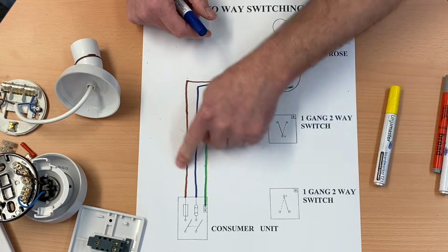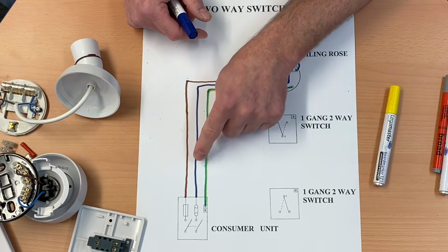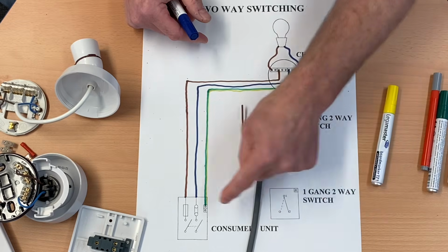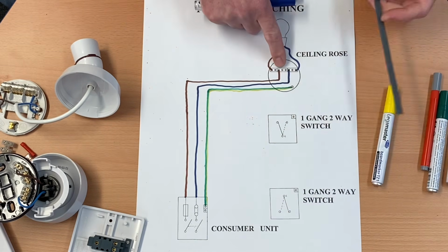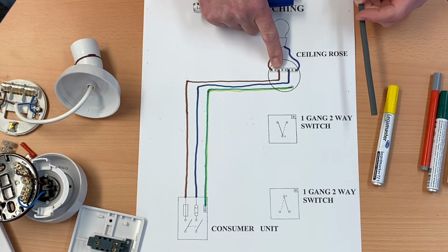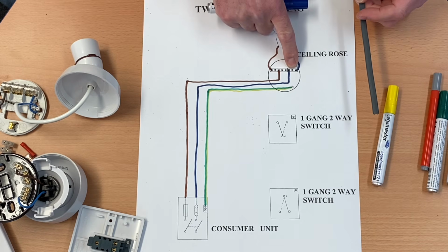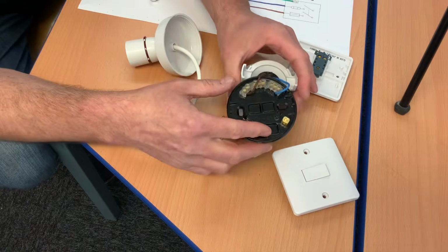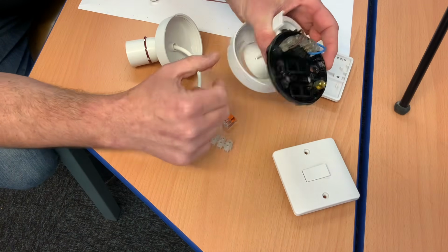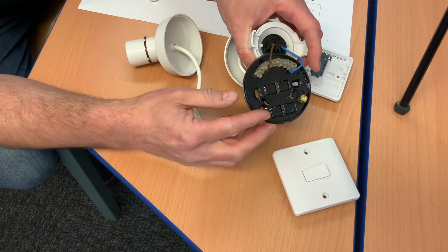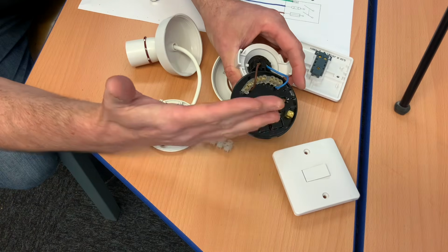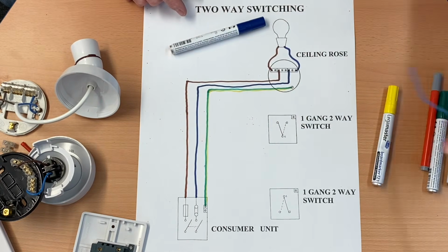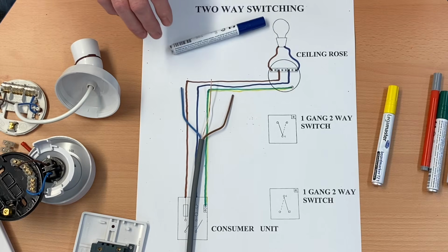Okay, so that brings our first cable in. So it's come from the consumer unit, line, neutral and CPC. So line, neutral and CPC is brought in like so. And it's connected into the loop, any of the 3, it doesn't matter which one. Into the neutral, any of the 3, doesn't matter. And into the terminal, which is for the circuit protective conductor, like so here. Remember, fully insulated, but it can be changed for a metallic fitting, which is an exposed conductive part in the future, and a CPC will be needed. So that's our 1mm squared cable coming in, identical to what we did in our previous video.